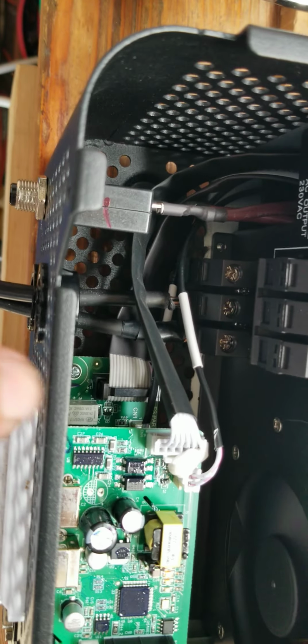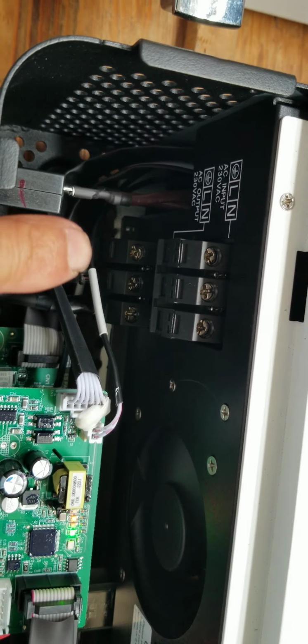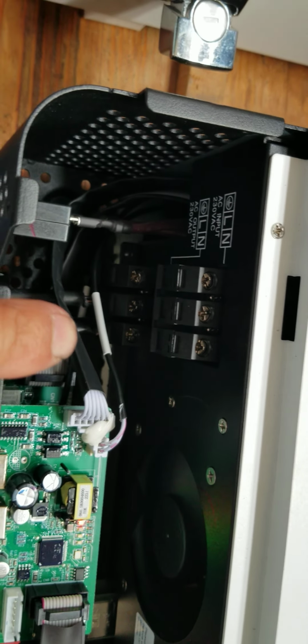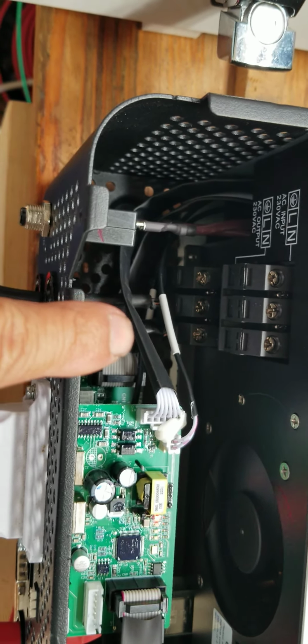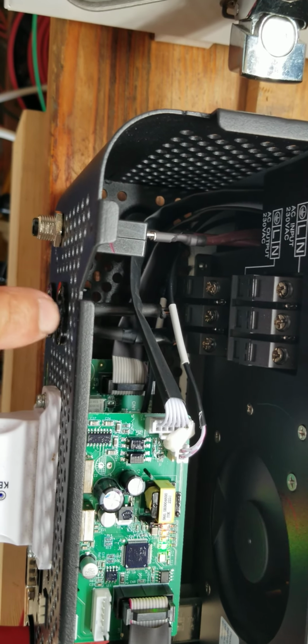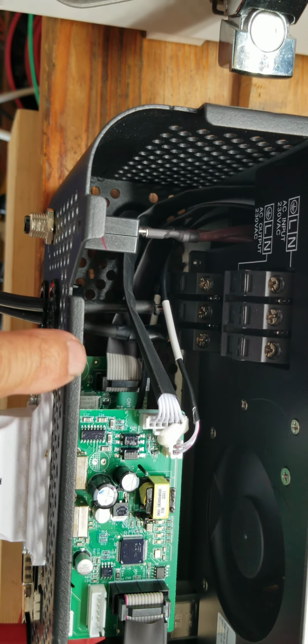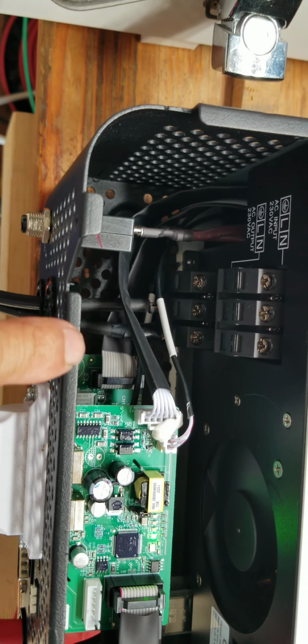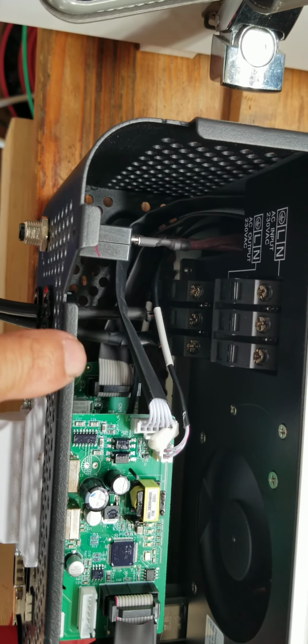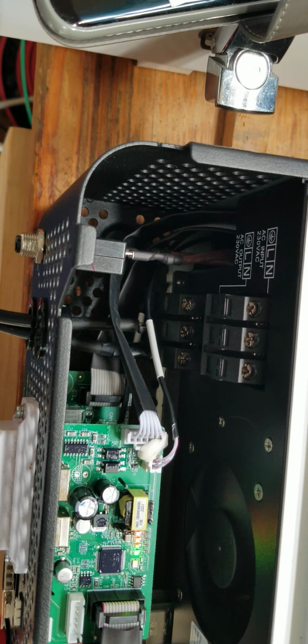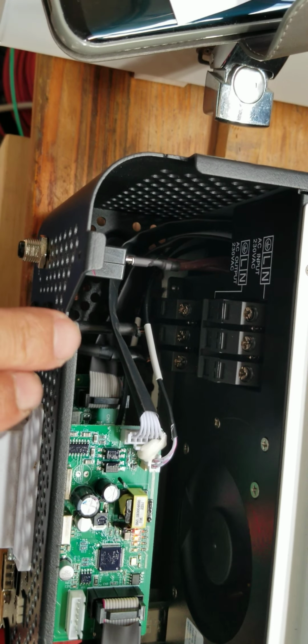Over here, which is the output, I don't use the ground because the ground and the neutral are still connected together. The neutral here is not the regular neutral, it's not the return wire - this one is a hot wire. Two of them come out, both hot, 240, 120 each.